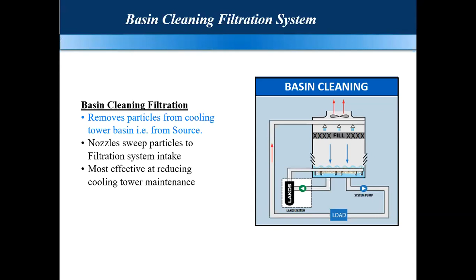Further to that, you can have a side stream filtration. Side stream filtration, as the name suggests, will take some portion of the flow rate. Say you have a cooling tower flow rate of 3000 USGPM. It's a 1000-ton cooling tower having a flow rate of 3000 USGPM. If you design a side stream system, you will be taking nearly 10 to 30% of the total flow rate, so it will be designed for 300 to 900 USGPM for the side stream.